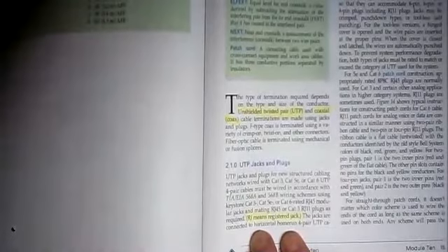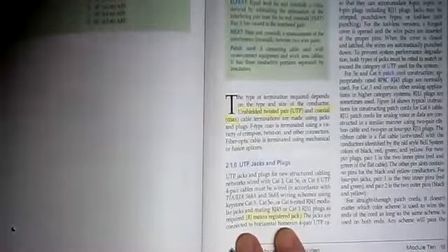That's one of the reasons why we stay away from transformers and motors 48 inches, because of that electromagnetic radiation. You have magnetic lines of flux coming out of those items, and it's going to interfere. It's going to induce a voltage and a current, and we're talking about very, very low currents. So any kind of an induced current will scramble the message that you're trying to send on that communications cable.